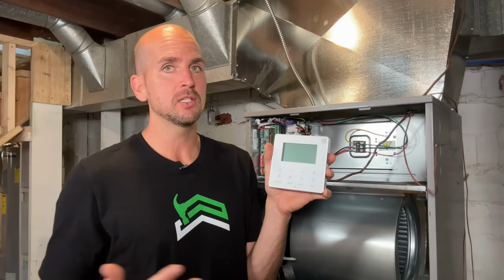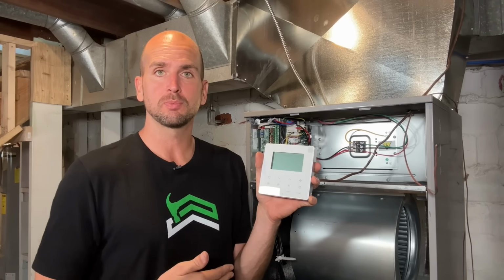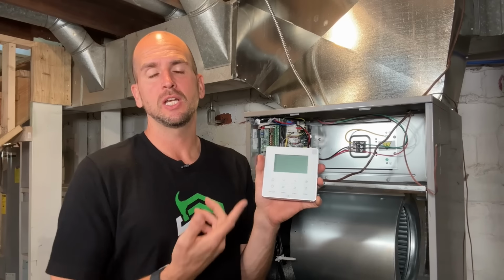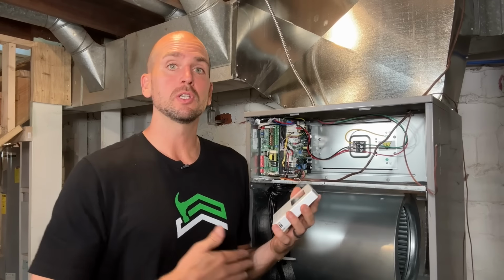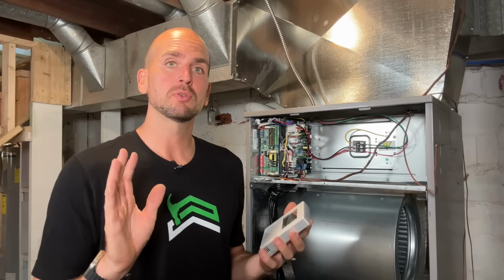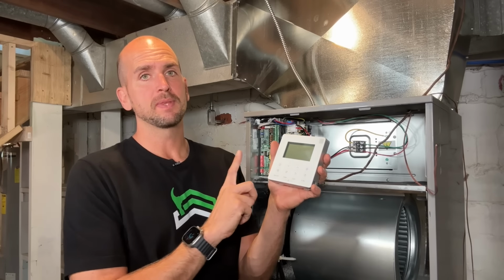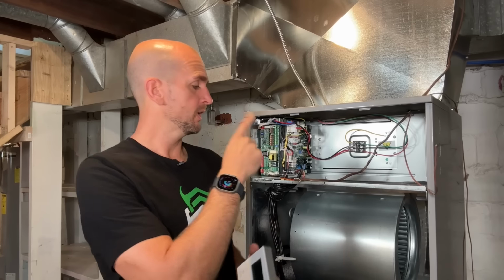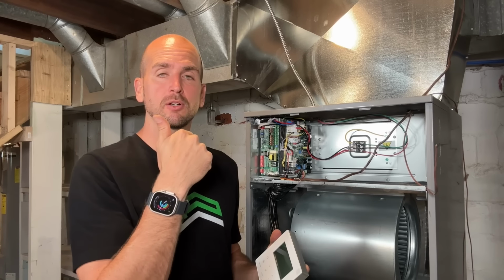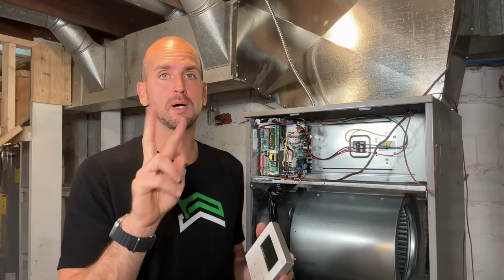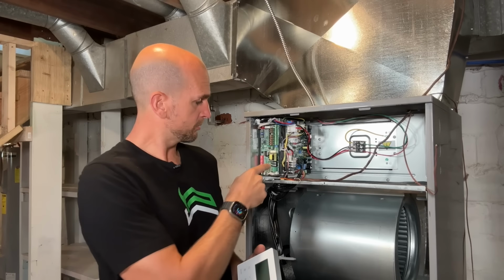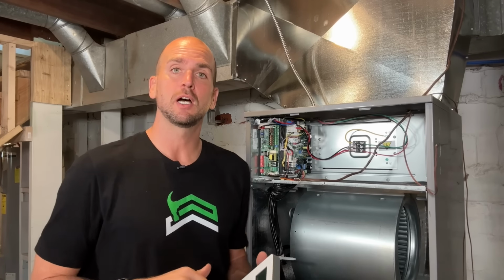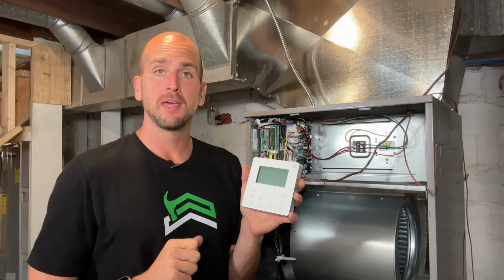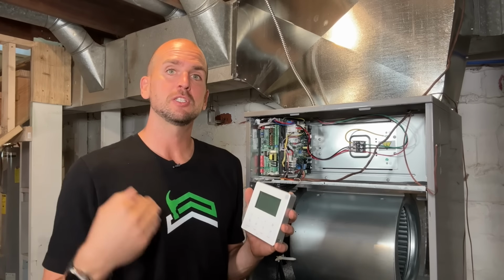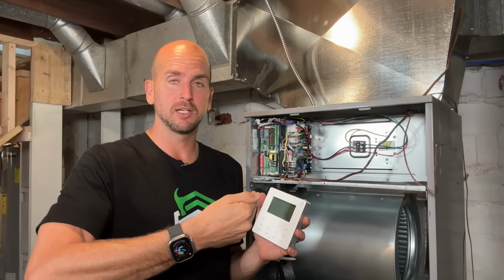Now I do understand you might be a fan of Nest or another smart thermostat, so you don't really want to change to a Mr. Cool unit. You want to stick with what you have, and you can do that. Just know that this Mr. Cool unit communicates between the air handler and the thermostat a little differently than most thermostats. You only need 2 wires to connect up. We're just going to connect up 2 wires here and then 2 wires up at the thermostat once we mount it. And then that provides it the ability to communicate between the thermostat and the air handler.